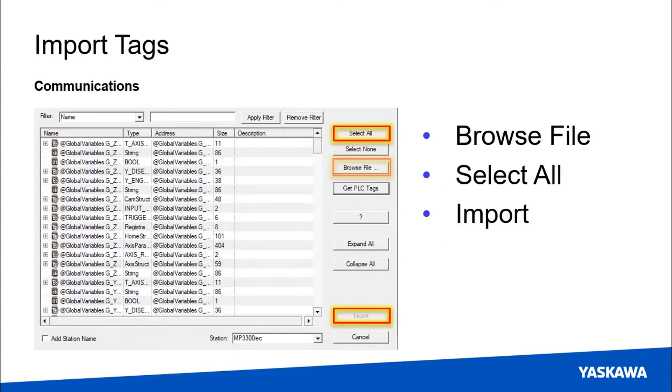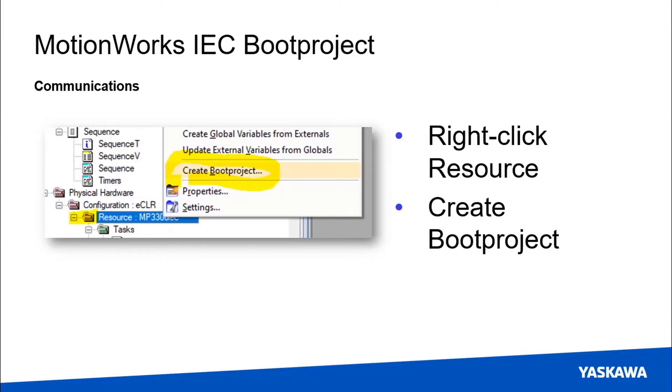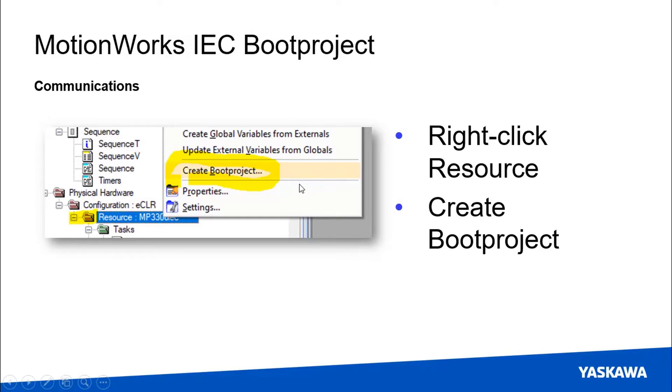When you get to the import tags screen this part's going to be a little different. Instead of getting PLC tags from the controller we want you to browse for a file. But in order for that to work you do have to go into MotionWorks IEC and right click on the resource to create boot project. You don't choose the boot project you choose MotionWorks IEC file but this boot project has to exist at the time of import to the HMI.